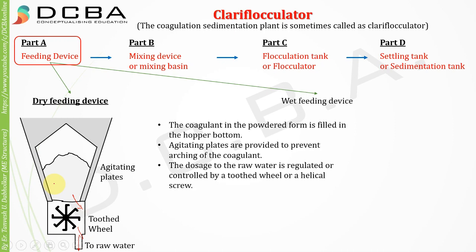The coagulant in powdered form is filled in the hopper bottom. Agitating plates are provided to prevent the arching of the coagulant — arching is when the powder hardens due to moisture. These agitating plates keep the coagulant moving, thus preventing arching. The dosage to the raw water is regulated by a toothed wheel or helical screw.